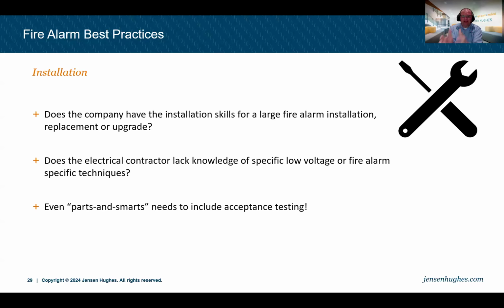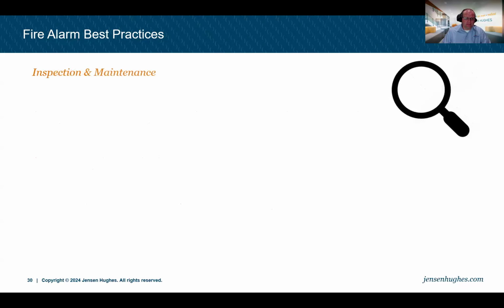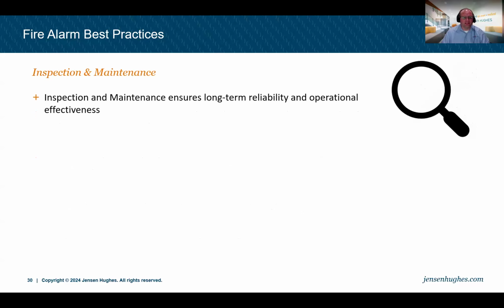Having the programming and having the devices needs to include some kind of acceptance testing and make sure all the equipment works together. It's really the best situations where a design meets the installation, where it meets the programming, and those three individuals work really well together to give you the best possible installation. And then finally, the ultimate success of a new or replacement fire alarm system is measured years later in the long-term reliability and operational effectiveness of the new system.